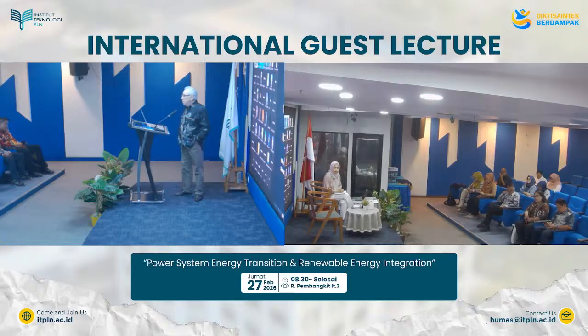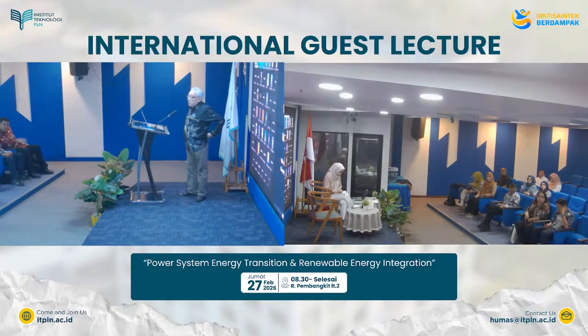So what happens when you've got 0.4 seconds to respond? This will become more and more the case as you introduce more renewable energy into the system through inverter-based resources. The inertia of present, thermal-dominated systems is about 5 seconds. On average you can take it down to 2 seconds, but we are heading towards a future where it will be 0.4 seconds. In some mini-grids with solar and diesel, you are there already. This requires new thinking and new planning tools.